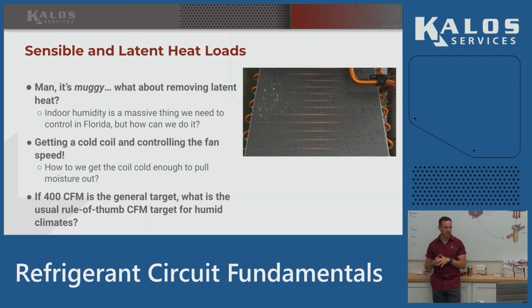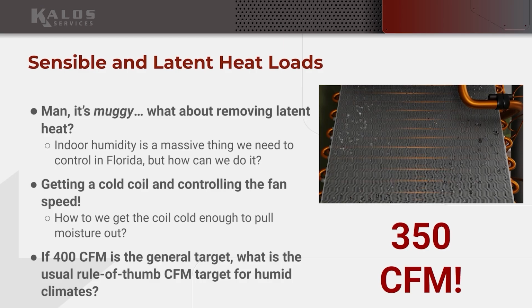It's also why we run our fan speeds lower. We're trying to not just cool the air, we also want to dehumidify, because that plays a huge role in comfort. So if I have a room, and you'll see this a lot of times during the winter, the room might be 72 degrees, but if my humidity is 70 percent, it still feels sticky and nasty in there, because I've got high humidity. So I want to dehumidify because it feels more comfortable to the customer. Usually we set our target humidity at about 54% or so.